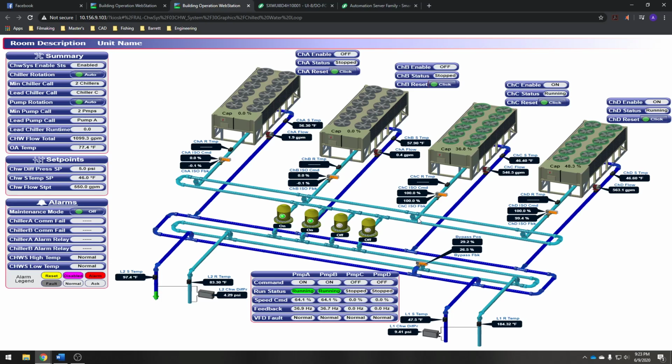We're literally thinking that water wasn't getting to certain parts of the data center because all the valves were wide open. The water didn't know where to go. There was no pressure to accomplish the flow that we needed. And since you guys didn't have flow meters, we had no idea what the flow is. We knew the chillers were maintaining minimum flow because they weren't shutting off.